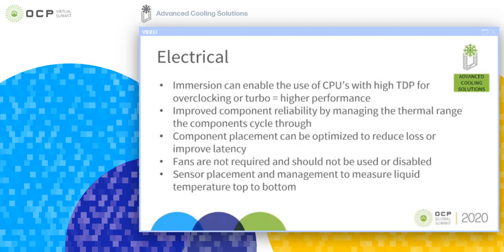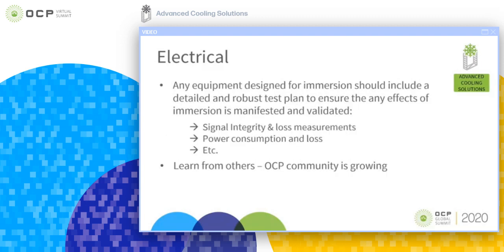And then component placement can be optimized to improve latency. In a lot of designs today, component placement is somewhat dictated by thermal management. So if that requirement goes away because you're immersing the components in liquid cooling, then you're able to optimize the performance by coupling components closer together, and in some cases reduce the latency that you might see. Fans aren't required. I think everybody knows that. And sensor placement throughout the system is really important to understand what's going on with the liquid cooling from top to bottom.